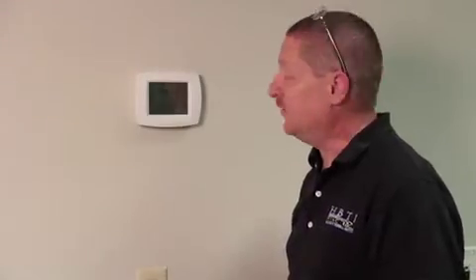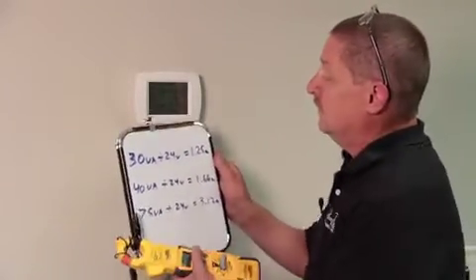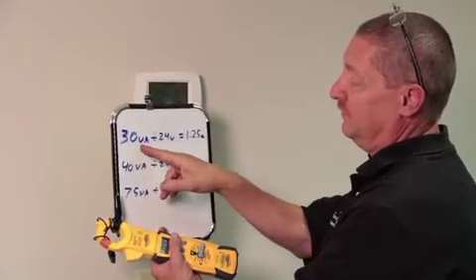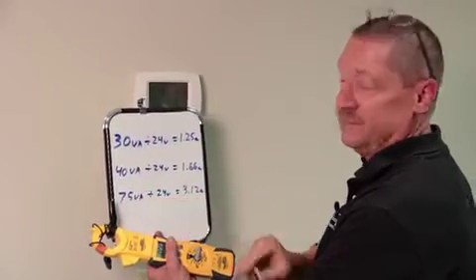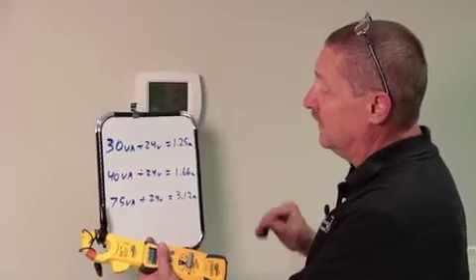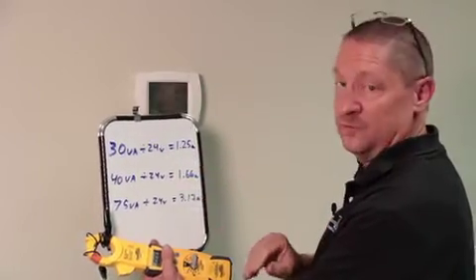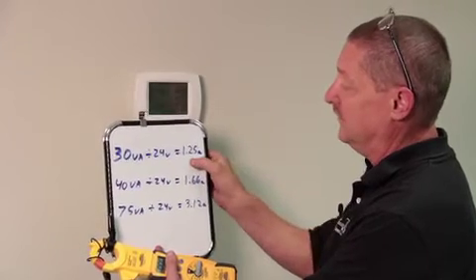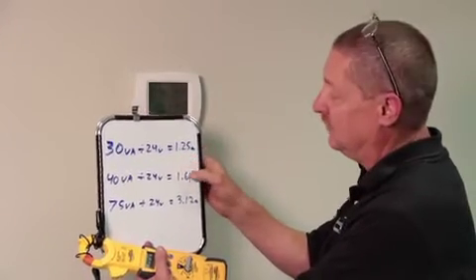We're talking about transformers and thermostats and low voltage problems. With the transformer you have the wattage - a 30 VA, 40 VA, or 75 VA transformer. If you divide that by the output voltage, you'll get your amperage that that transformer is good for. A 30 VA is for a standard furnace.